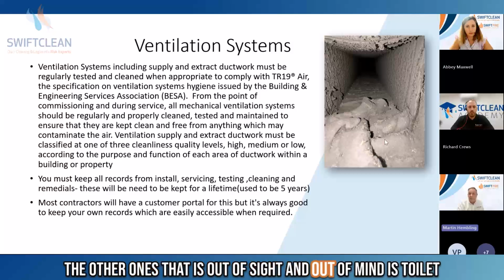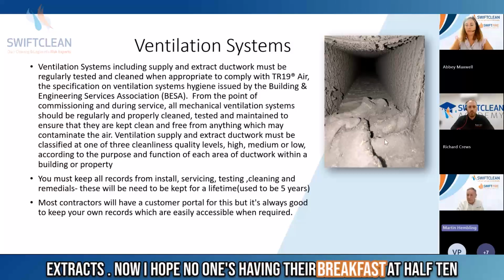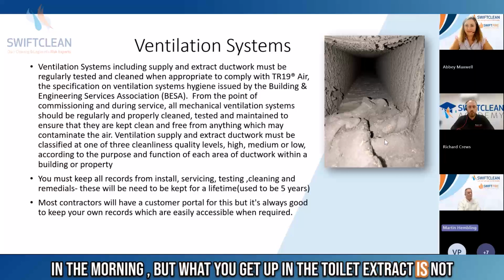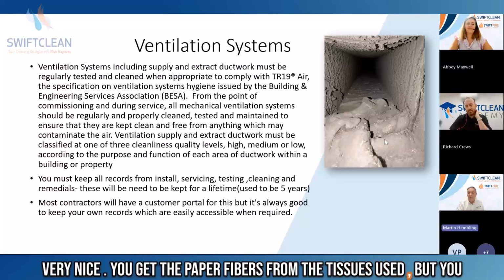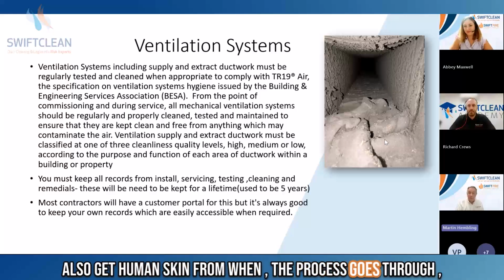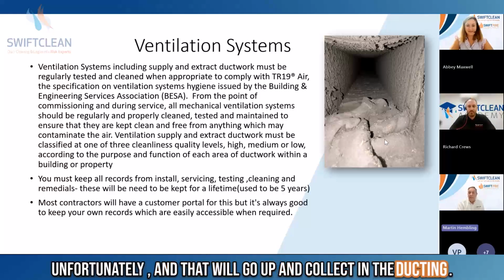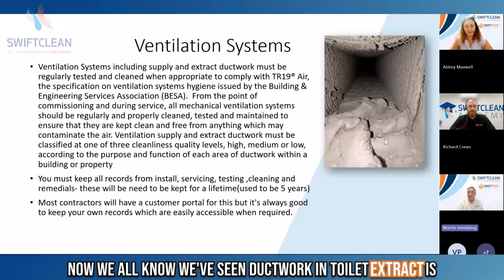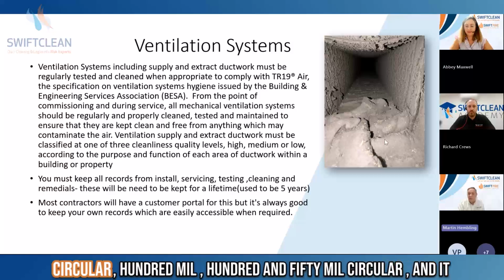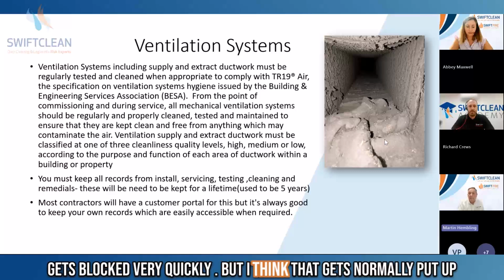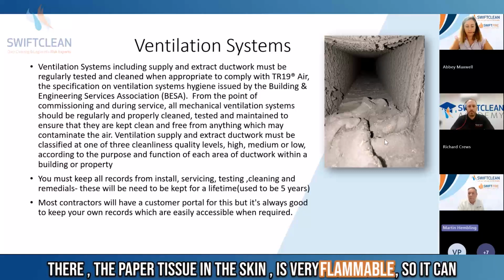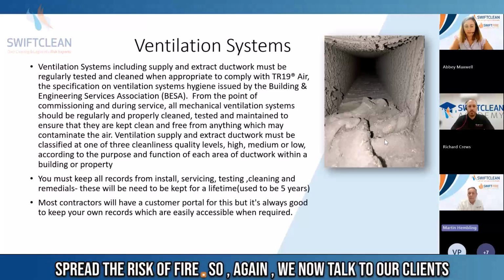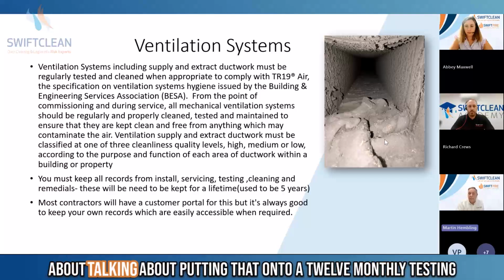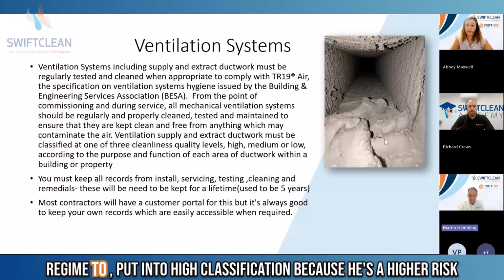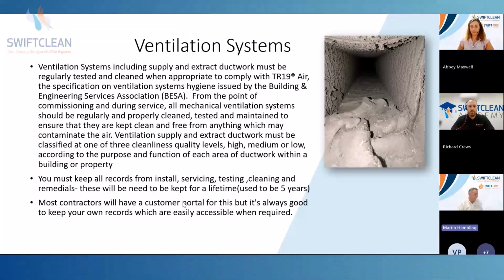And the other ones that is out of sight and out of mind is toilet extracts. Now, I hope no one's having their breakfast at 10:30 in the morning, but what you get up in the toilet extract is not very nice. You get the paper fibers from the tissues used, but you also get human skin from when the process goes through, unfortunately, and that will go up and collect in the ducting. Now, we all know, and we've seen, ductwork in toilet extracts is normally the smallest ducting on the building. It's normally circular, 100 mil, 150 mil circular, and it gets blocked very quickly. But everything that gets normally put up there, the paper tissue and the skin, is very flammable, so it can spread the risk of fire. So again, we now talk to our clients about putting that onto a 12 monthly testing regime, to put it into the high classification because it is a higher risk.